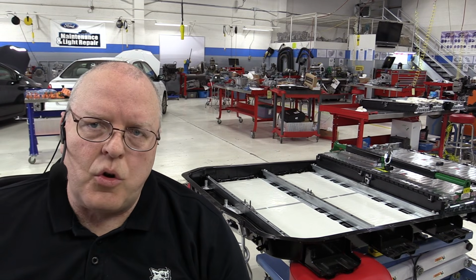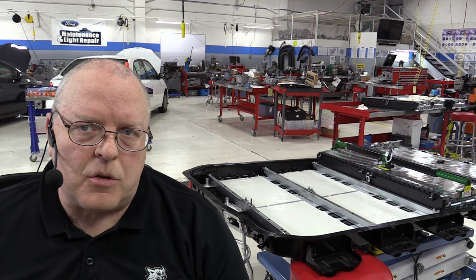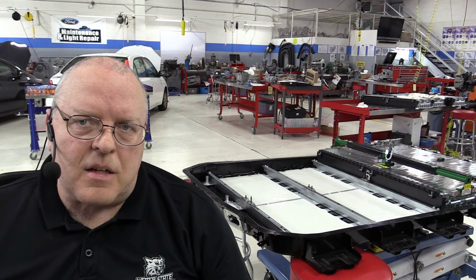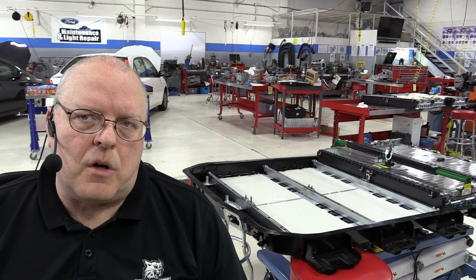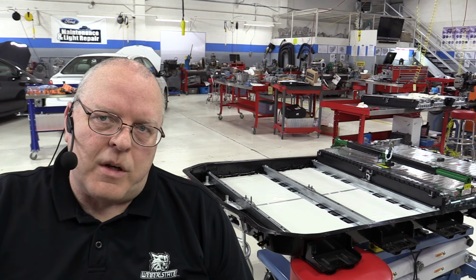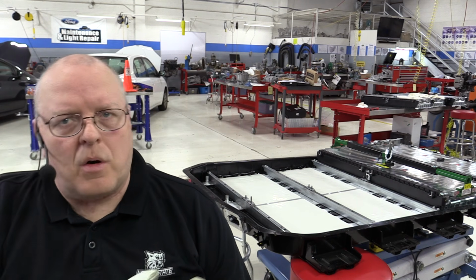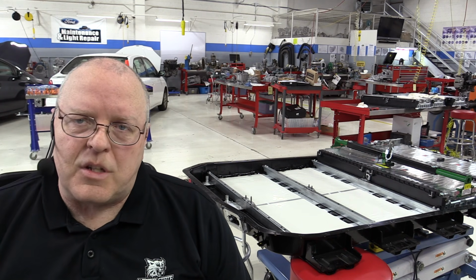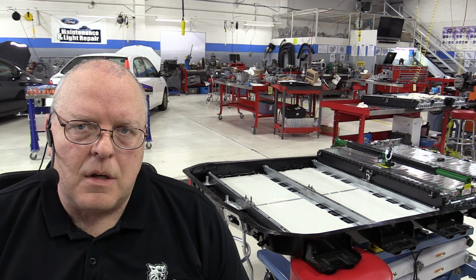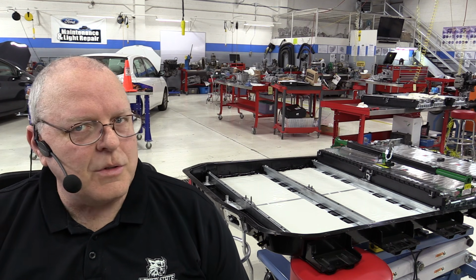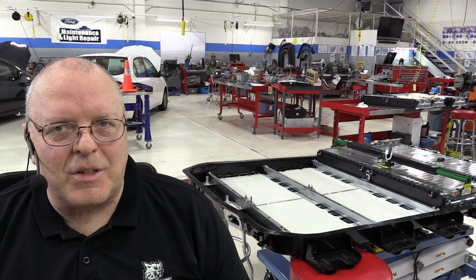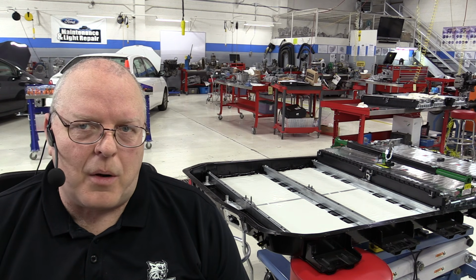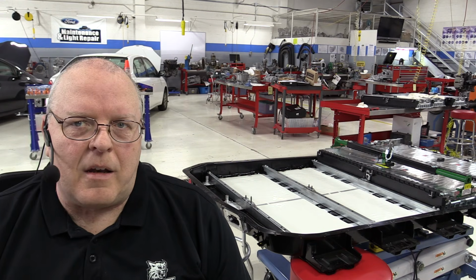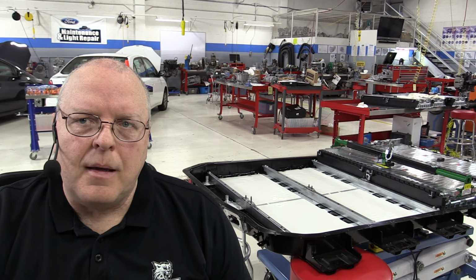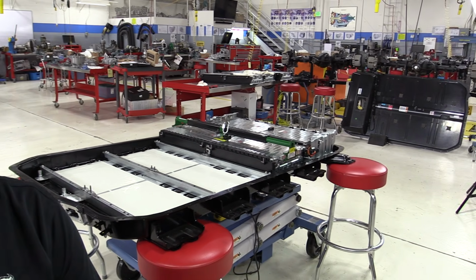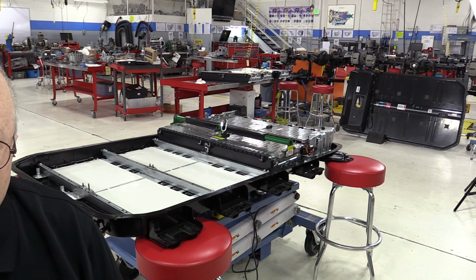Although battery section 2 may look just like battery section 1 and 3, it actually has opposite polarity terminals, allowing the batteries to be put in series on the left side of the battery housing and the right side of the battery housing. So never get those mixed up — always mark which section is which, and double check the polarity so we always have positive going to negative with those big bus bars. Alright, let's bring the crane in and get battery section 3 out of there.